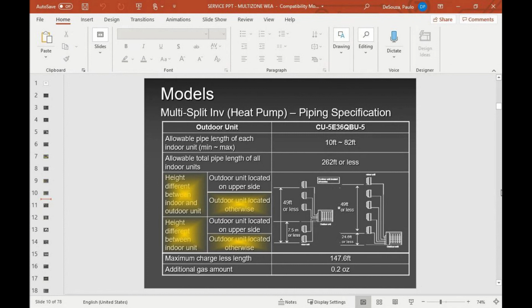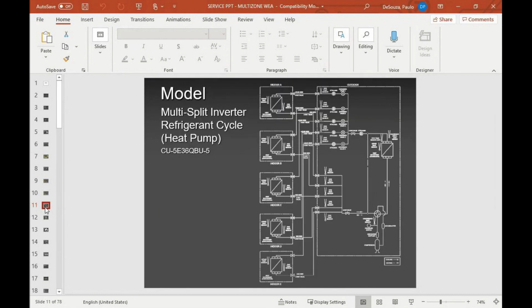Here you go. Height difference between the bottom of the outdoor unit to the bottom of the lowest indoor unit: you have to maintain 49 feet. Okay? Indoor to indoor, 24 feet. Same applies when the outdoor unit is at the bottom. So in the earlier slide, the outdoor unit was on top. In this slide, the outdoor unit is at the bottom, and in this slide, the outdoor unit is in the middle.